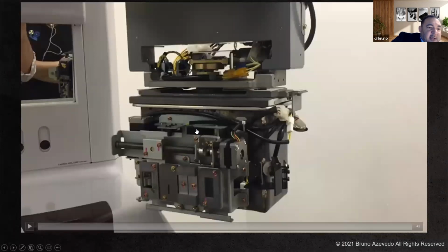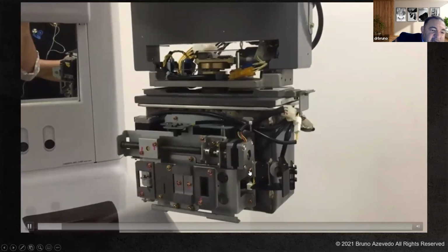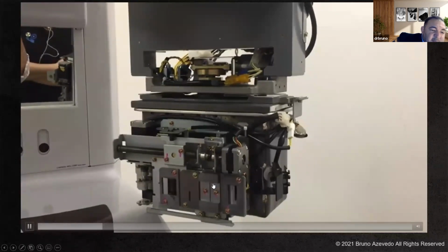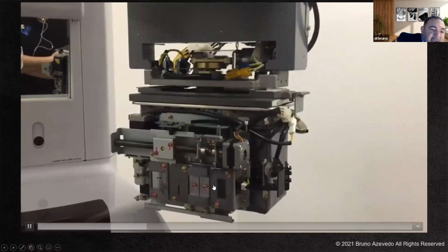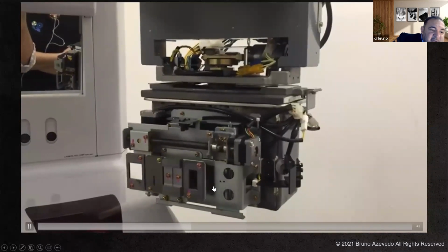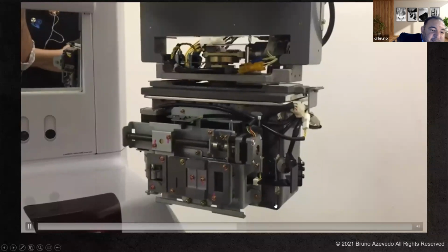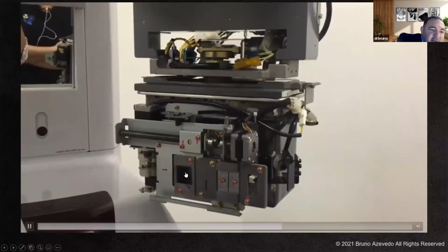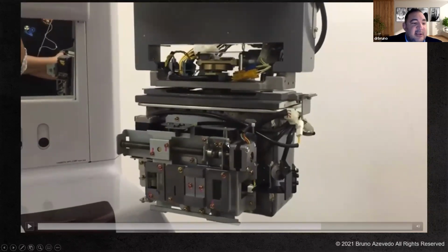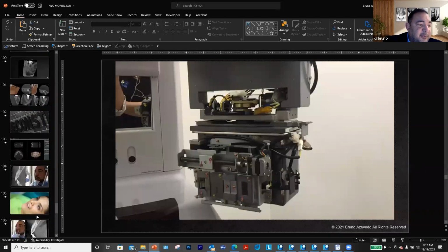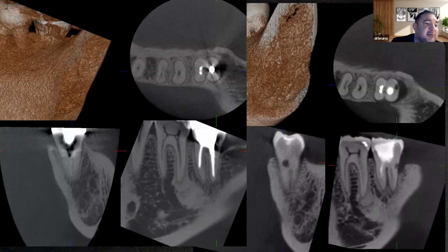And what is the difference between Morita with 100 kV and all the others with 120 kV? It is that when we select the endo module on the Morita, it takes away what's called the copper filter of the unit. There's a copper filter coming up and down when you're changing your acquisition. One of the things that Morita does is on the endo module, it actually removes the copper filter. The filter filters that 120 kV and creates a lot of noise on the volume on the other side. So the fact that Morita can remove that copper filter is one of the reasons why we can actually increase the resolution instead of decreasing the resolution.